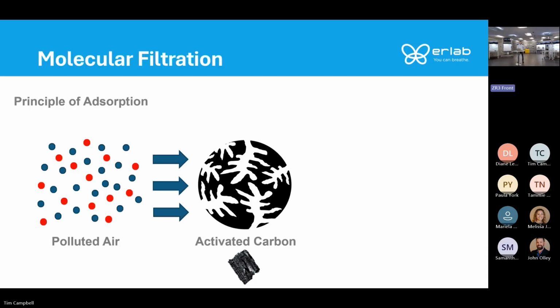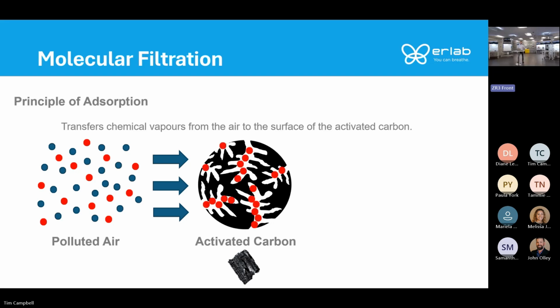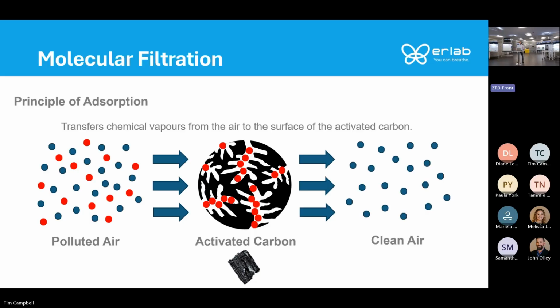The air from the fan, the flow, pulls that polluted air away from the end user and up into the filtration column. And this is where the chemical vapors then adsorb to the carbon. They adhere to the surface of the activated carbon. And that's why having more surface area allows for more retention capacity. And then as the air goes through, on the exhaust side of the carbon filter is that clean air. So you're pulling air in from the lab away from the user. Those chemical vapors go up with it. They go through the carbon filter. Clean air is returned to the lab.